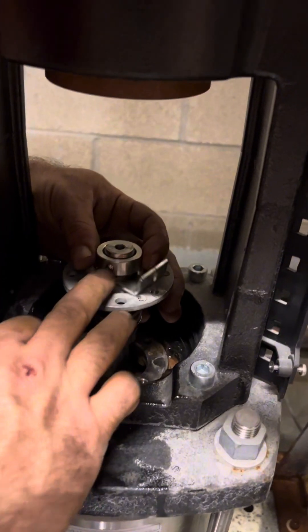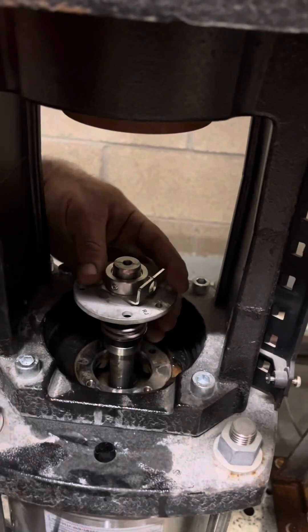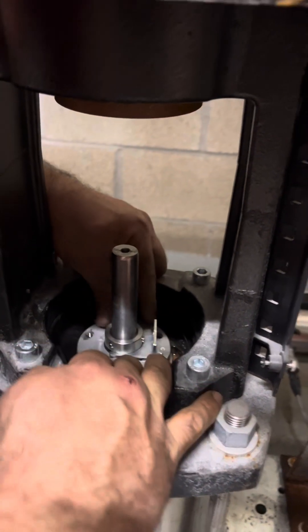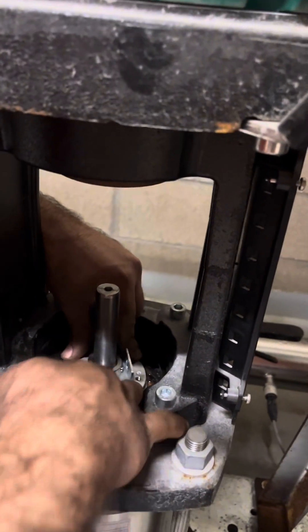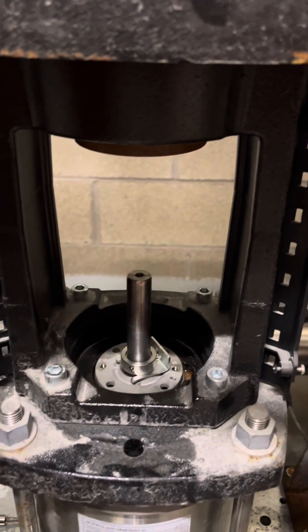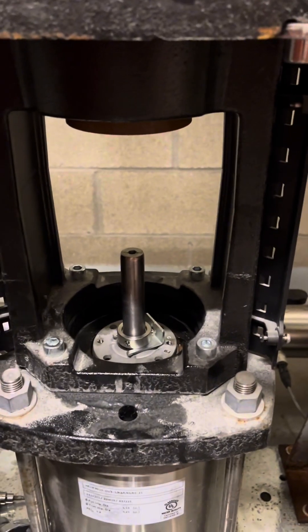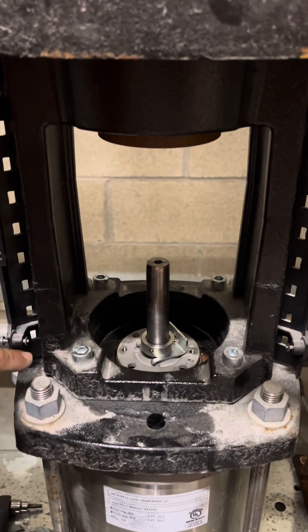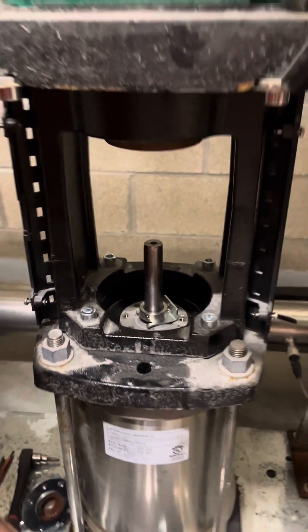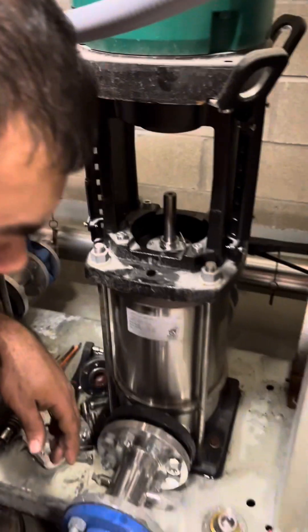If you had to loosen these screws on the bracket, it might not let it slide down good, so go ahead and slide it all the way down like that. Line up with those bolt holes. The mechanical seal kit comes with new screws to put in here, so you don't want to put those old rusted ones back in there. I'm going to dab them with just a little bit of anti-seize so they don't run the risk of getting stuck in there.